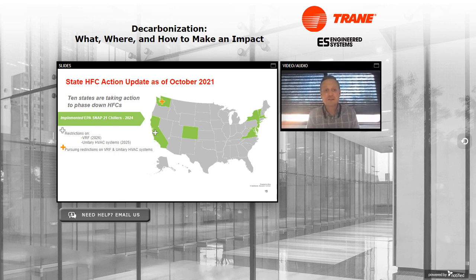The 10 states in green have all phased out R134A and R410A in chillers starting January 1st, 2024. California has gone one step further, phasing out 410A in unitary equipment in 2025 and VRF equipment in 2026. AHRI, the common body for HVAC manufacturers, petitioned the US EPA as an industry to adopt rules similar to California's—phasing out chillers in '24, unitary in '25, and VRF in '26. The US EPA did accept that, and we think by the end of next year those rules will be in place across the country.